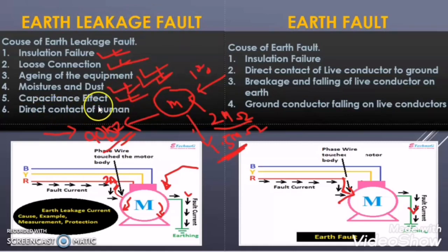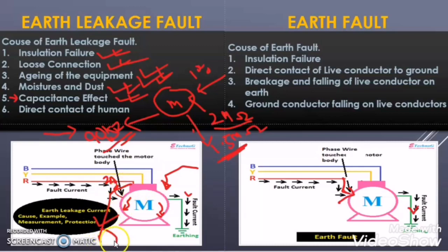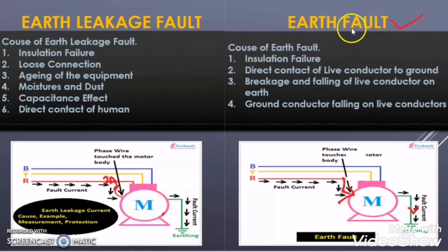Capacitance effect — I will not talk much about this one because it is related to electronic devices, but it is a fact that the capacitance effect also causes the earth leakage fault condition. The direct contact of a human is another cause. Suppose everything is perfect — insulation is perfect, there is no loose connection, the motor is new, no moisture — but anybody comes and by mistake touches the terminal of the motor. Then some current will flow from the human body to ground. So this is also one of the reasons for earth leakage fault. In all these conditions, the current is flowing through the winding of the motor and a small current is leaking from the motor winding to the body of the equipment, with no phase loss in the motor.